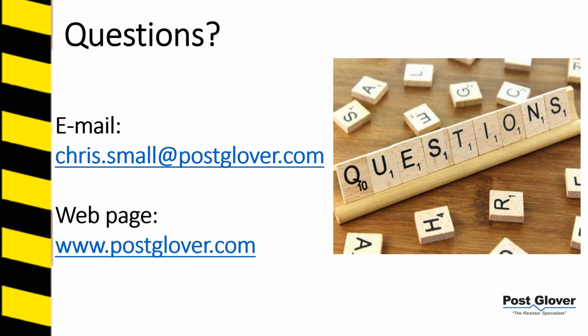I know that you can. Well, for medium voltage, I can't think of an example, but I'm sure there are delta-oriented phase correction capacitors. Whenever you have a piece of equipment that has a capacitor on it, you're going to be drastically impacting the capacitive charging current. For some things there are ways around it, and one of those ways is to hook it up delta. You can't do that with everything, but it's a good example. The phase correction capacitors usually can be hooked up and not line to ground.